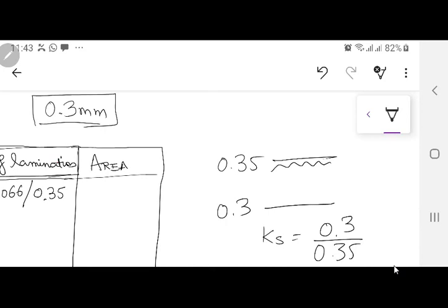I'm again repeating. If you have a lamination of thickness 0.3, when you add insulation it can be 0.33, 0.34, 0.35 or even 0.37. If you put a little thicker lamination insulation, okay, that depends on your worker, whether he applies it thick or thin, totally up to you.